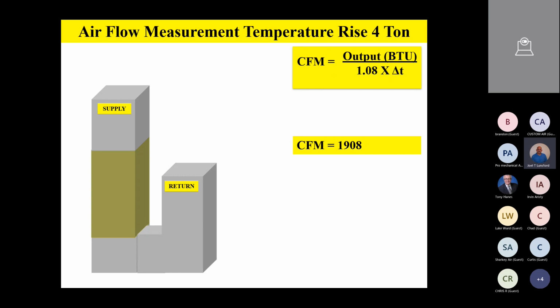But now hang on a second. Sometimes you can blow too much air, can't you? Especially in your market down there in the Florida market, if you're blowing too much air across the coil, your humidity control goes in the toilet. So you want to be blowing between 1550 and 1600 on a 4-ton unit at a nominal 400 CFM per ton.